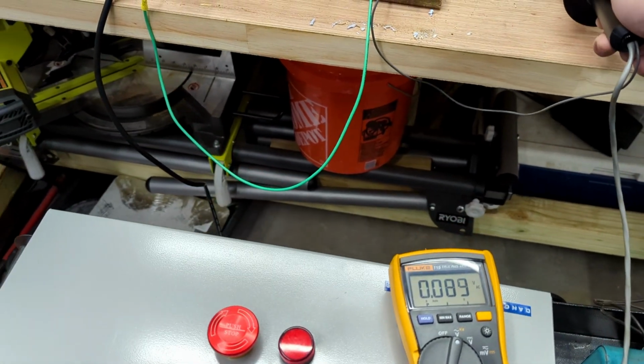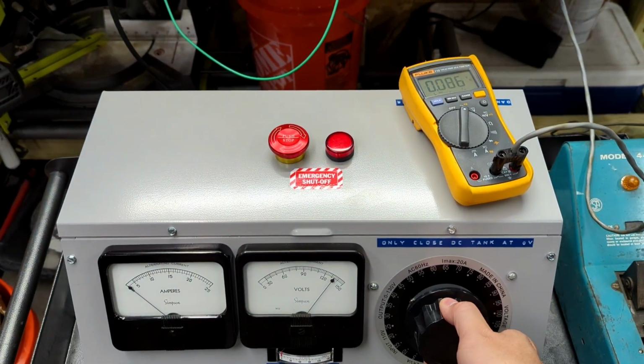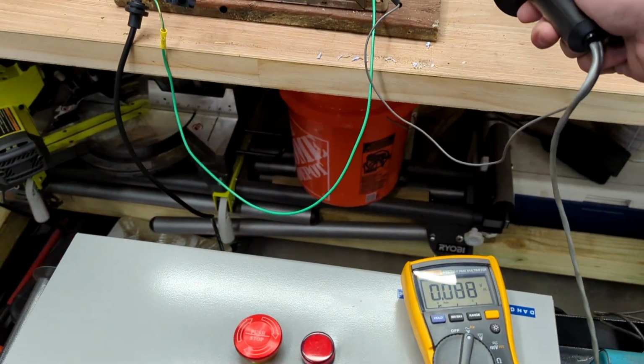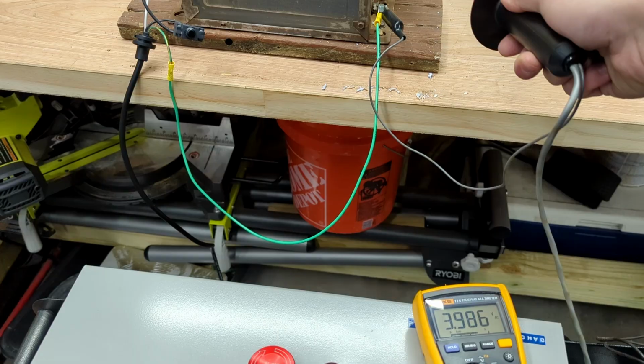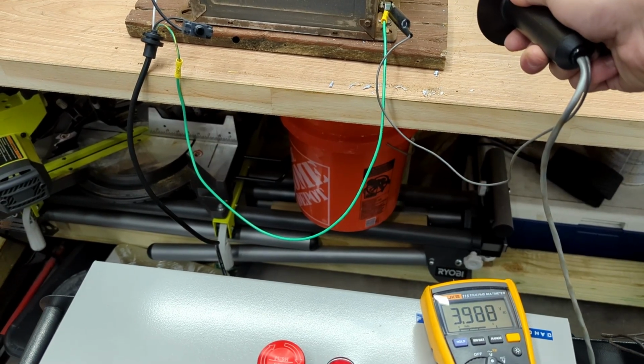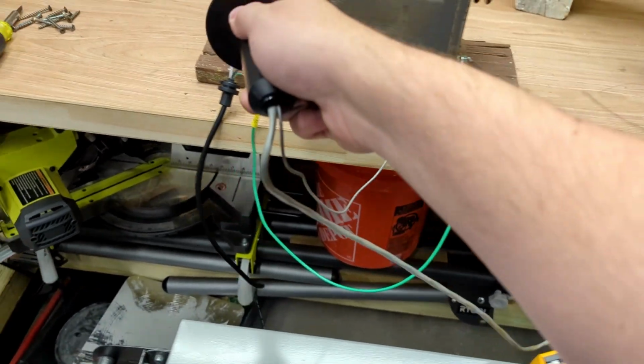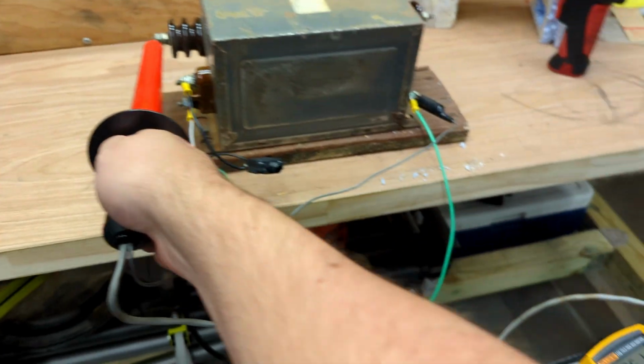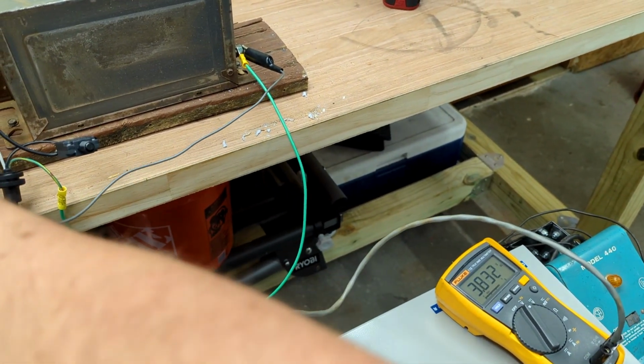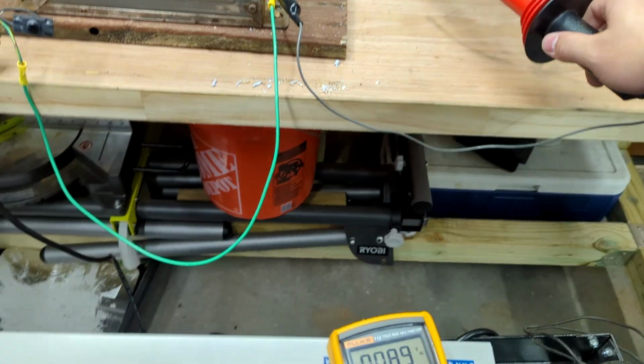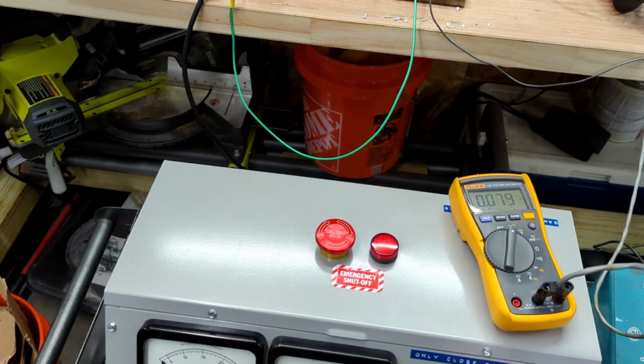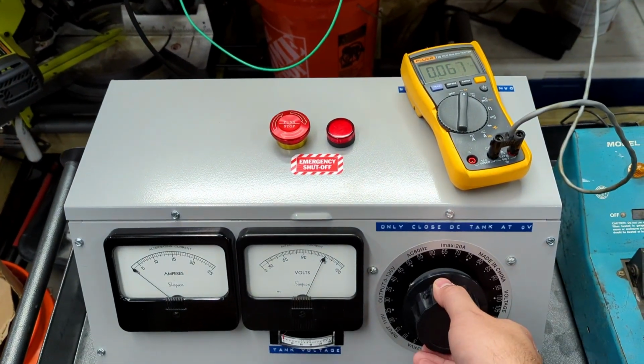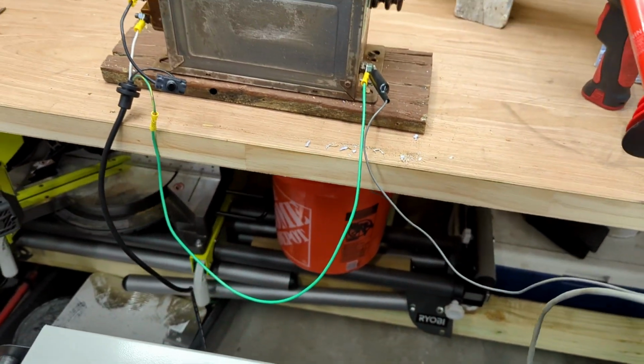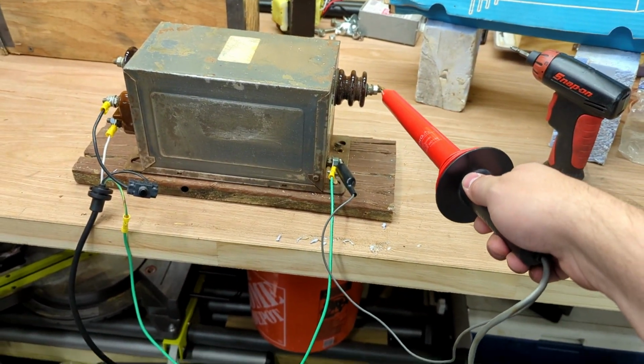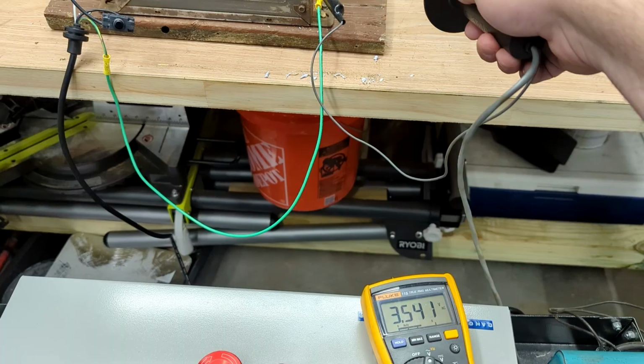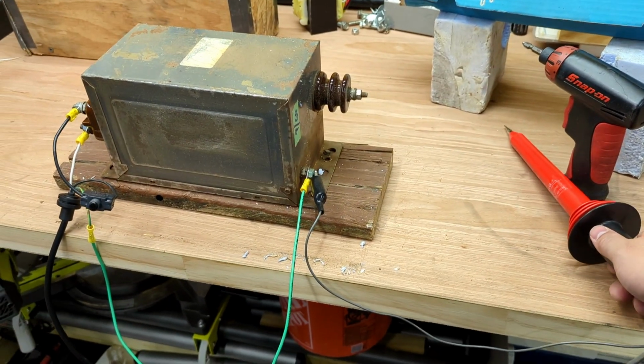So I need 4 kV per side. You can feel some good humming coming from the table. There we go. 3.9 kV. I would never recommend doing this without a high voltage probe. Turn it back down to 120. So the way that some people will test them, and you can test them this way, at 3.5 kV, would be to...